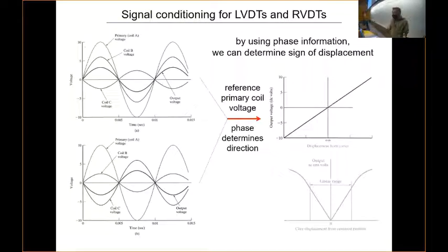And that varies depending, there're two different load resistances that you look at. I can't remember which, but one of them is, I think just because of the circuitry within that decade box, a little bit longer. But you might see anything from, say, 3 degrees to 30 degrees. And then when you switch over to the other side of the displacement, so it's out of phase, you should see whatever you saw, that 3 to 30, plus the 180 degrees.